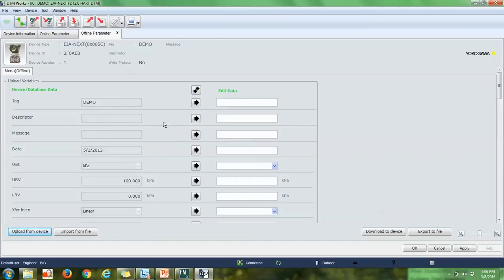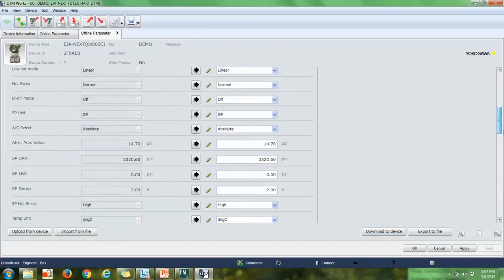I'm going to copy all these parameters into my workspace. The workspace is where you can make adjustments. Instead of making changes point by point, you could make a lot of changes in this list because every parameter is listed, and then just adjust it that way. So I'm in my workspace. Let's change something. We'll change this to 90 kilopascals, and we'll change the transfer function to square root. I could download this to the device, and then every parameter would be updated.